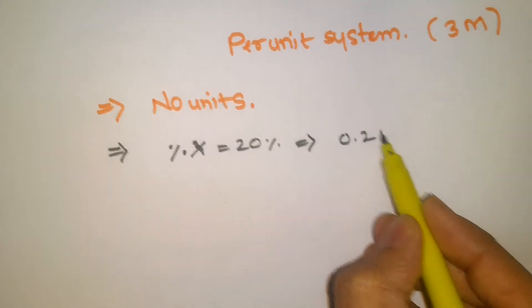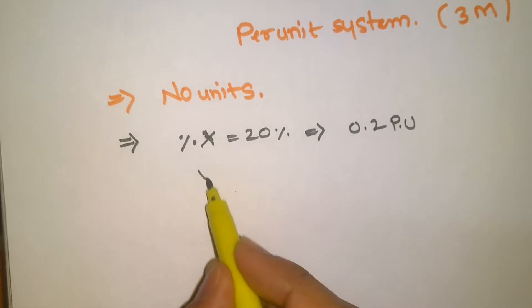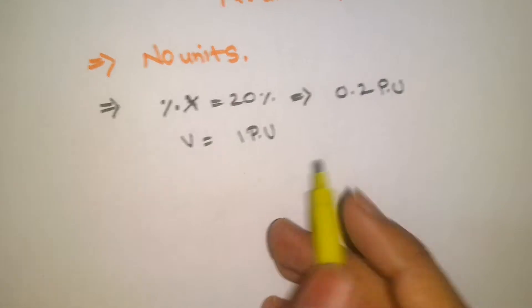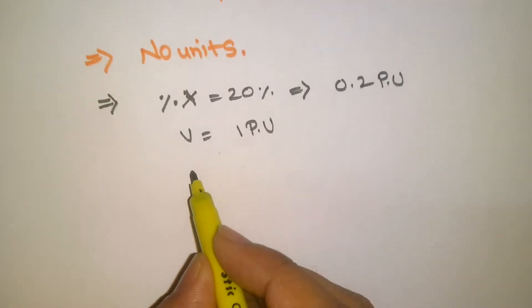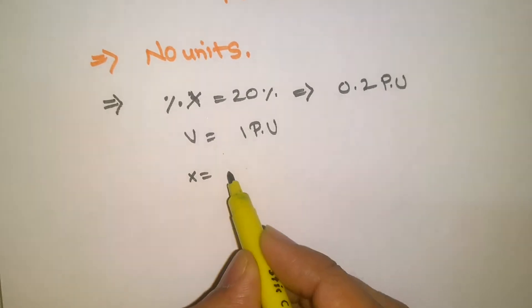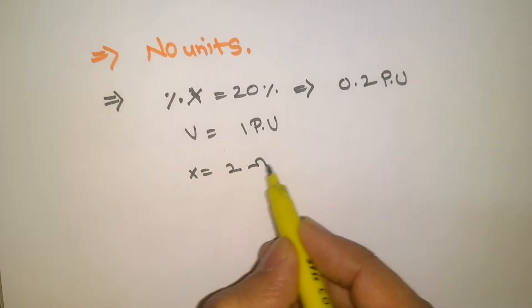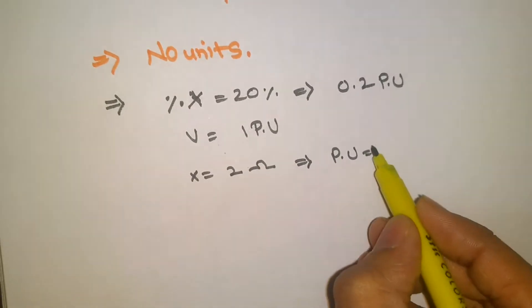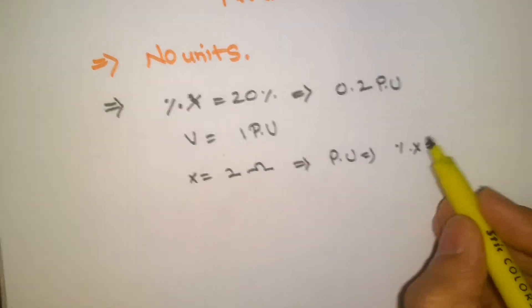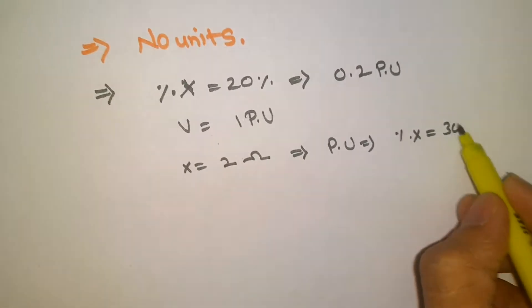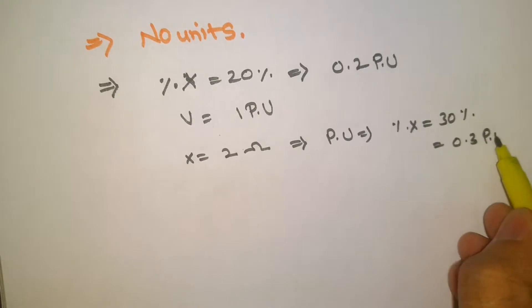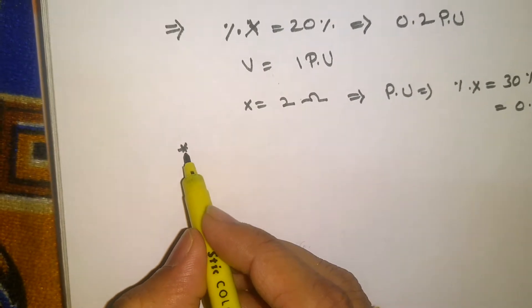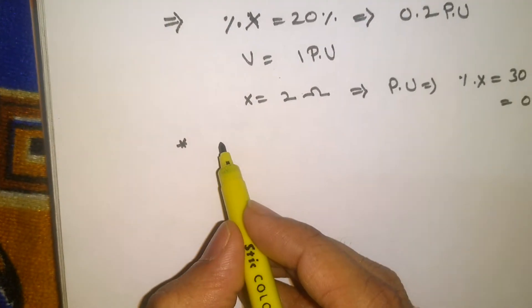If percentage impedance is 20%, we convert it to 0.2 per unit. If voltage is 1 per unit, this is the per unit system. In the actual system we say X is equal to some 2 ohms, but in the per unit system we use percentage of X — say 30% — so 0.3 is the per unit value.